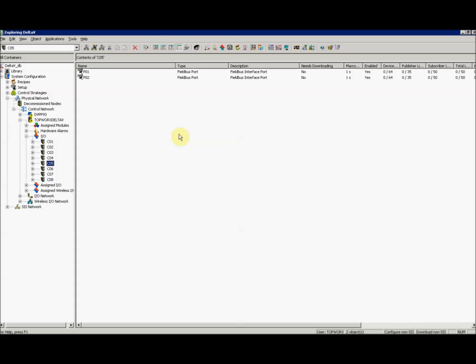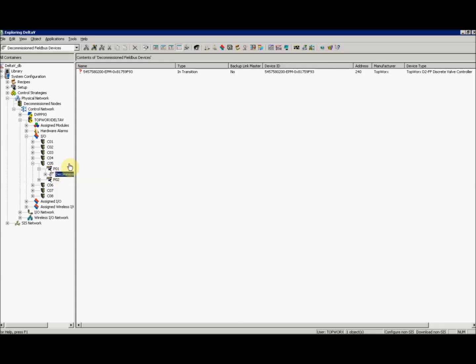About commissioning a device. In DeltaV Explorer, find your controller and then select the I/O section of that controller and go down to your H1 card. In our case, the H1 card is card 5. I've terminated our device on port 1, so we'll look in port 1 under Decommissioned Fieldbus Devices. Here you should see your device, and it should be in standby. If it's not in standby, go ahead and place it in standby.